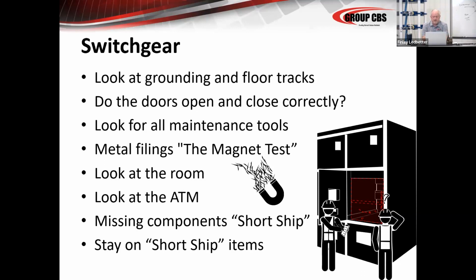The metal filings or magnet test: I always carried a fairly powerful magnet in my toolbox because I was a field guy in the beginning, so I'm from that world. After the breakers were installed, I would always go back and look on the bottom of the switchgear doors, under cabinets, underneath the racking devices and the mechanisms to see if there were any metal filings. If you've got metal filings after you've opened and closed the breaker 10 or 12 times and racked it in once or twice during acceptance testing, imagine how many metal filings are going to be there in a couple of years. That means there's a problem.